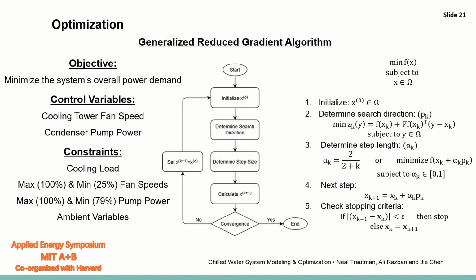The constraints that were in the optimization were the cooling load determined through the cooling load prediction algorithm, the minimum and maximum fan speed, and the minimum and maximum pump power. The minimum in this case was to maintain turbulent flow through the chiller, and then also the ambient variables collected from the time point of the optimization.